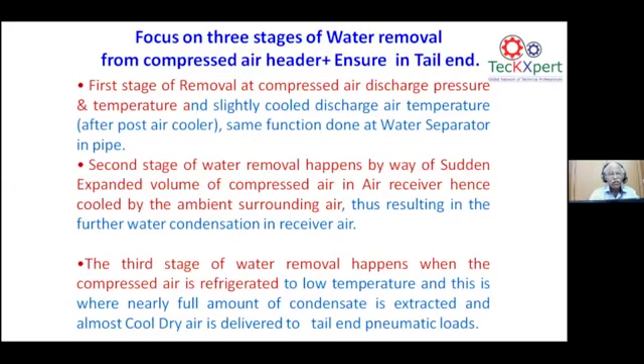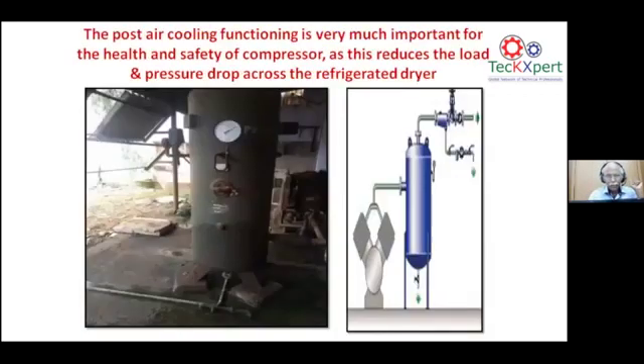Next is the third stage, where in the refrigerator dryer the existing air is cooled down and the water is sucked out of the refrigerator dryer. So all the three stages have to work in the existing compressed air system, especially in the compressor house. This will see to it that the compressor is healthy and the compressed air is healthy. You can see almost a quarter of the compressor air receiver is filled with water. In many of your air receivers, if you leave it for a day, almost a quarter of your receiver is full, and this is going to cause a lot of malfunction in all your pneumatic systems at the tail end.